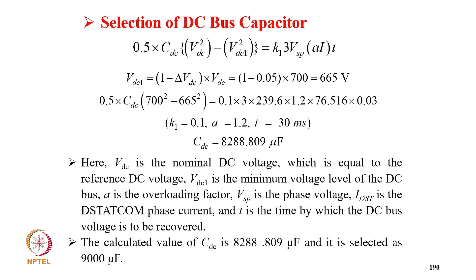Now coming to the selection of the DC capacitor. From energy balance we say 0.5 into CDC times (VDC square minus VDC1 square) equals K1 into 3 VSP into A into IDST into T, where solving this CDC comes around 8,288.809 microfarad. Here VDC is the nominal DC link voltage, which is equal to the reference DC voltage, and VDC1 is the minimum voltage level of the DC bus. A is the overloading factor, VSP is the phase voltage, IDST is the DSTATCOM phase current, and T is the time by which the DC bus voltage is to be recovered. The calculated value of CDC is 8,288.809 microfarad, and it is selected as 9,000 microfarad. And coming to the selection of an AC inductor, LR equals root 3 M VDC divided by 12 A F times ICRPP. So from this LR comes around, putting the values, 6.113 millihenry.